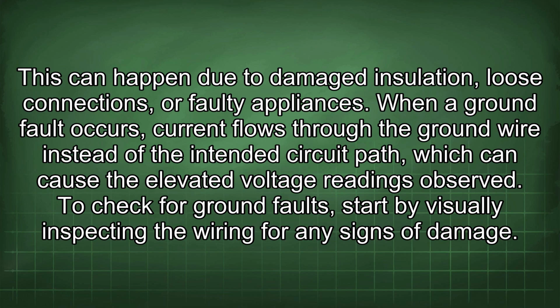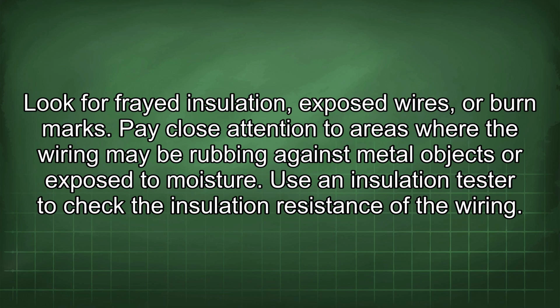To check for ground faults, start by visually inspecting the wiring for any signs of damage. Look for frayed insulation, exposed wires, or burn marks. Pay close attention to areas where the wiring may be rubbing against metal objects or exposed to moisture.